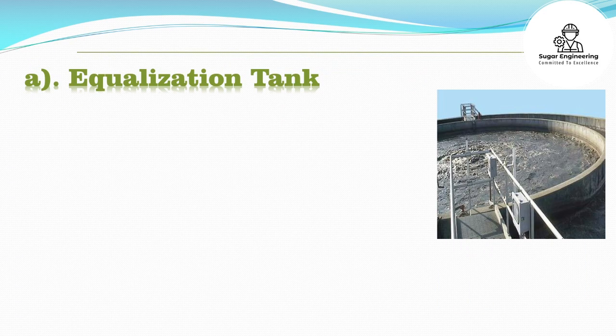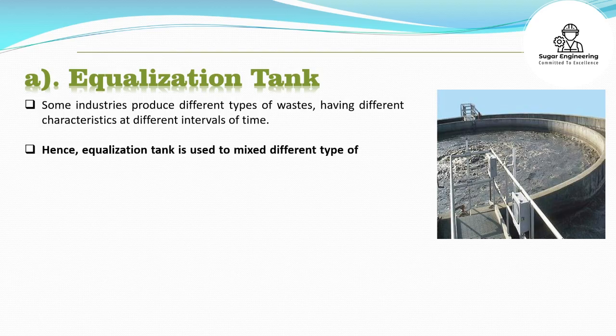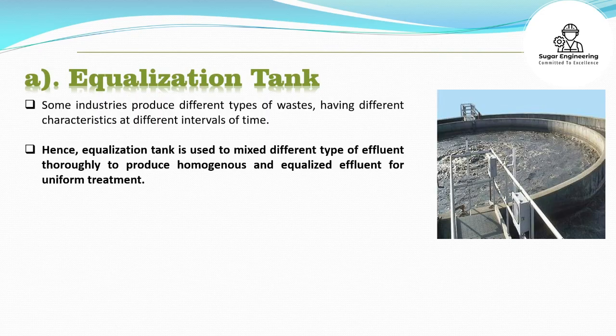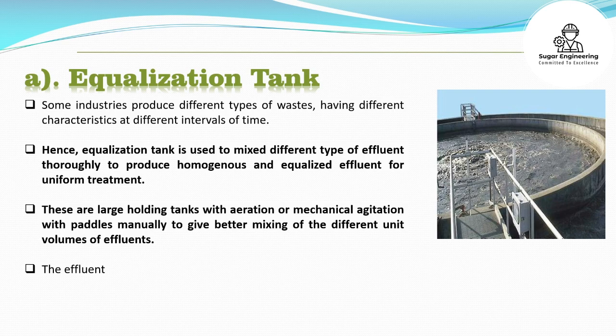Equalization Tank: Some industries produce different types of wastes having different characteristics at different intervals of time. Hence, the equalization tank is used to mix different types of effluent thoroughly to produce homogenous and equalized effluent for uniform treatment. These are large holding tanks with aeration or mechanical agitation with paddles to give better mixing of the different unit volumes of effluents. The effluent is held and mixed for a specified period of time.